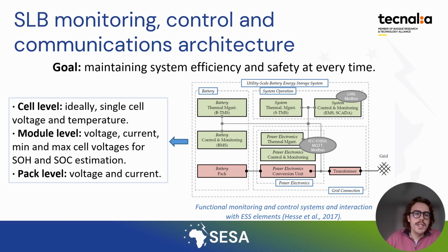So internally, all these data are communicated using different protocols like Modbus TCP, CAN, or RS485. Moreover, external communication with the electronic device or the PCS, the grid, or other elements external are carried out using also protocols like Modbus TCP, MQTT, or the IEC 61850.